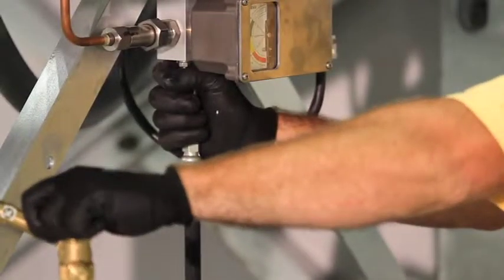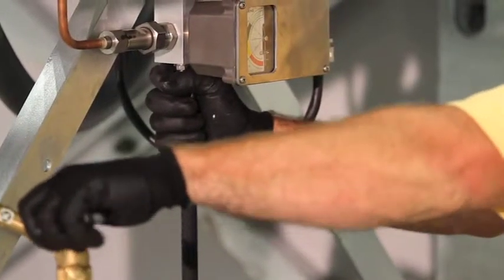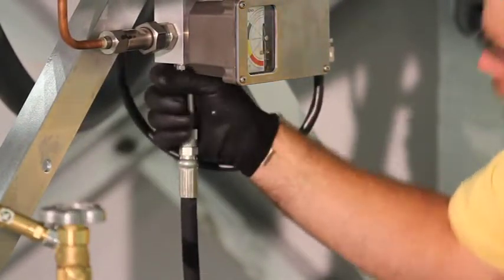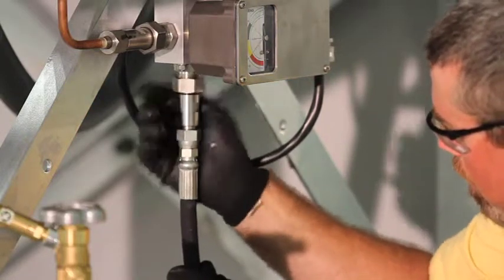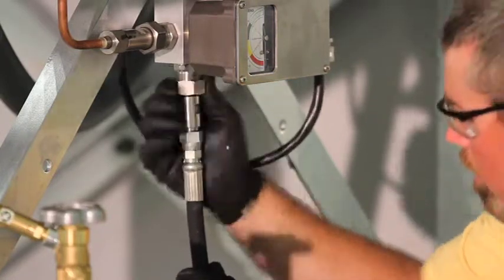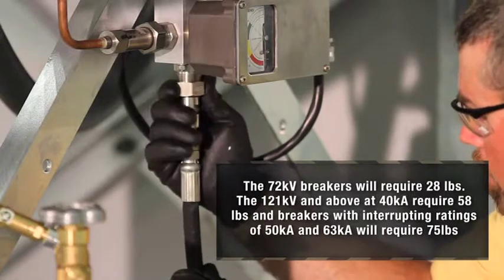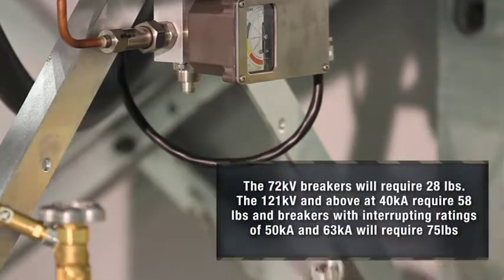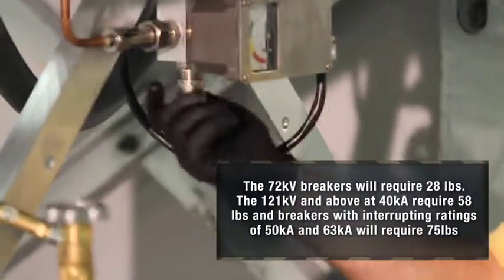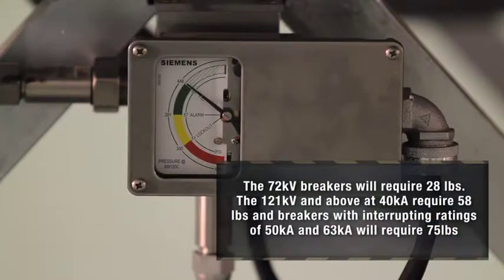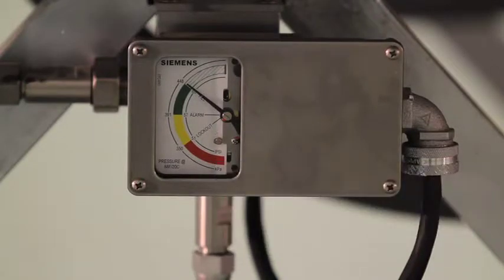The amount of SF6 gas required to fill the breaker varies with the kilovolt and kiloamp rating. When the proper fill level is reached, shut off the SF6 cylinder valve and disconnect the quick disconnect fitting. Reinstall the cap on the breaker service fitting. Check the fill level after 24 hours to ensure correct reading is made.